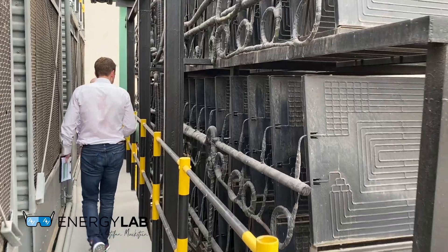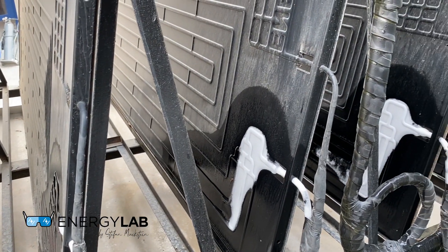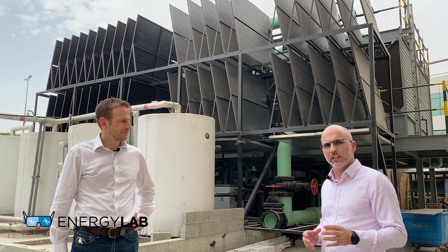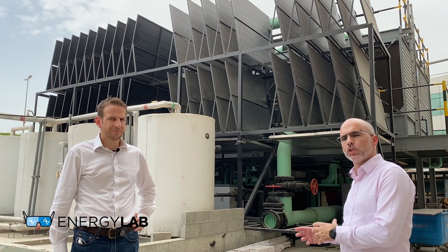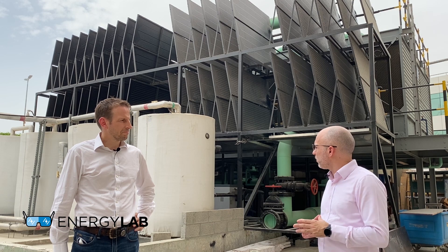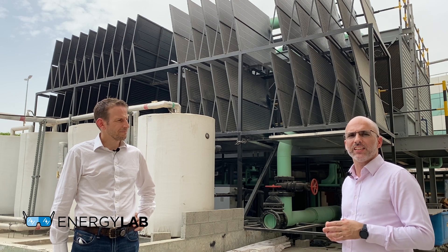That's the beauty of it — normally systems have the cooling side and the heating side. For us, it's more important to heat the water, but if our panels are producing a byproduct which is collateral cooling, the cooling towers are eager to get it. What is happening here is that the air is flowing through our panels, cooling down about 10 degrees, also reducing the humidity, entering the cooling towers, making the cooling towers much more efficient. On the other side, the cooling towers are dissipating our cooling faster, and therefore our system can produce more hot water per day if required. So this symbiosis creates higher efficiency. This system is producing around 41 cubic meters of hot water per day plus recirculation, at a daily cost of only 197 dirhams per day.